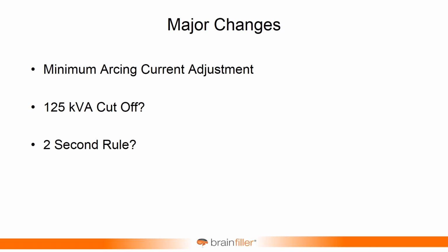The 2-second rule, back in the 2002 edition, there's the case, and it still exists, where you may have a situation that you have a lower arcing current, and the time current curve of the protective device looks like it's going to have a clearing time that's going to wait until like next Tuesday or something like that. I mean, kind of an exaggeration, but you get the idea.